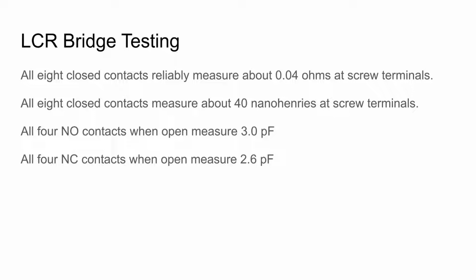However, at low resistances, the measured resistance depends strongly on test probe pressure. At reasonable handheld pressure, regardless of wiggling hands a little, I reliably measured about 4 hundredths of an ohm on all 8 closed contacts at the screw terminals. That's a bit less than half the relay datasheet's maximum specification, which is excellent performance.